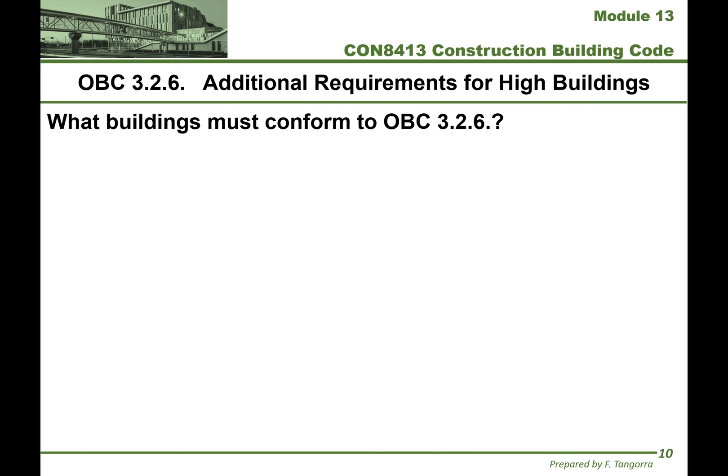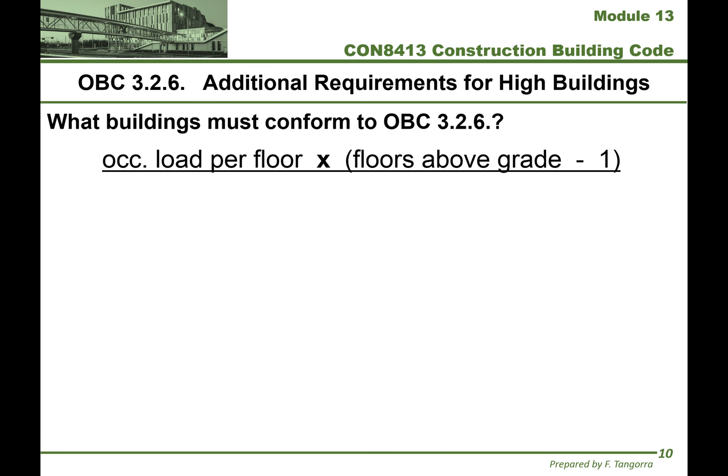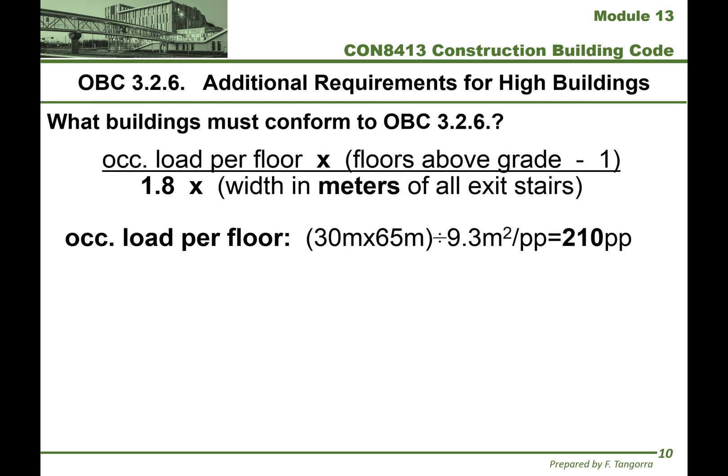This is what the formula basically says. It's a fraction where the numerator is the occupant load per floor times the number of floors above grade minus one. All of this gets divided by 1.8 times the width in meters of all exit stairs — not just one, but all of them. The occupant load per floor is the area of the floor plan — 30 meters by 65 meters — divided by the factor from a specific table in the building code. For office, that factor is 9.3 square meters per person.